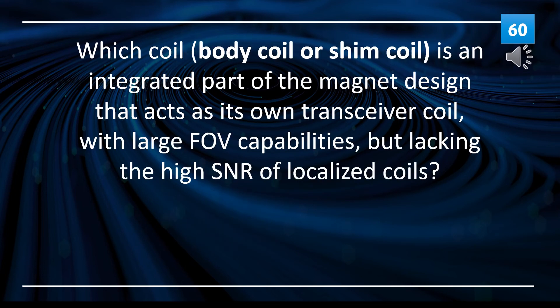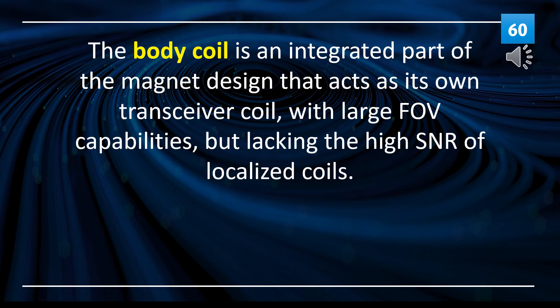Which coil — body coil or shim coil — is an integrated part of the magnet design that acts as its own transceiver coil, with large field of view capabilities, but lacking the high SNR of localized coils? The answer is the body coil.